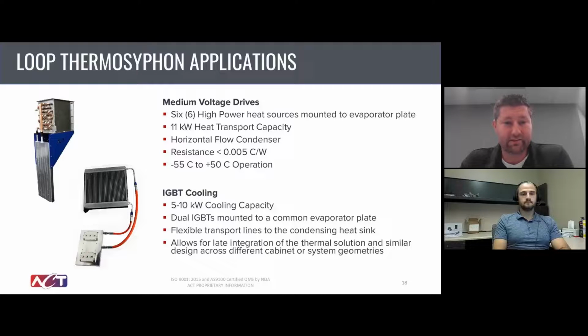So that exact example, you can see some of the figures there, had an extremely low thermal resistance, so very low temperature gradient across those areas. And we were able to operate that system between -55 and +50 degrees C and transfer and reject over 11 kilowatts of heat. So a very capable solution in a fairly small form factor. That entire solution fit within a medium voltage drive cabinet with only the condenser exposed to the air environment.